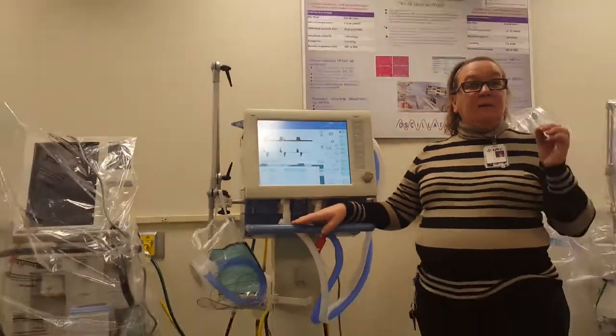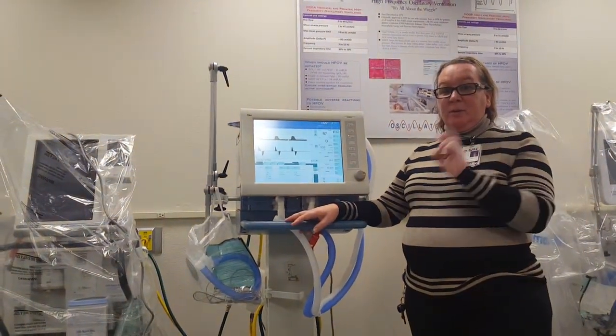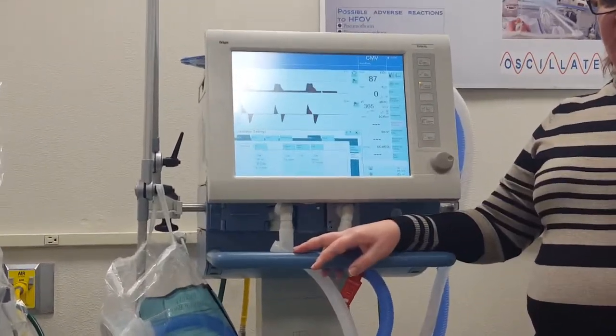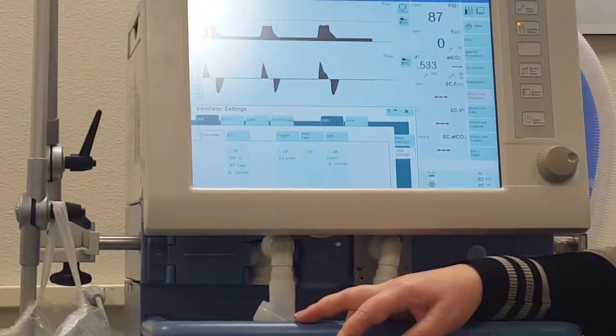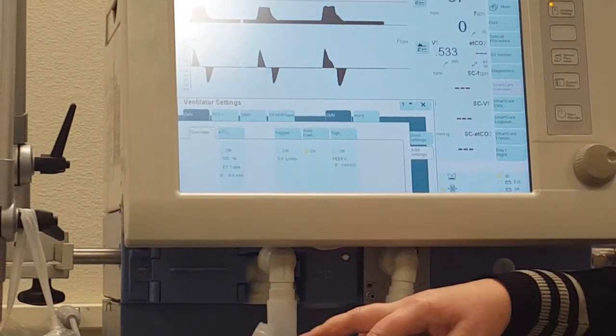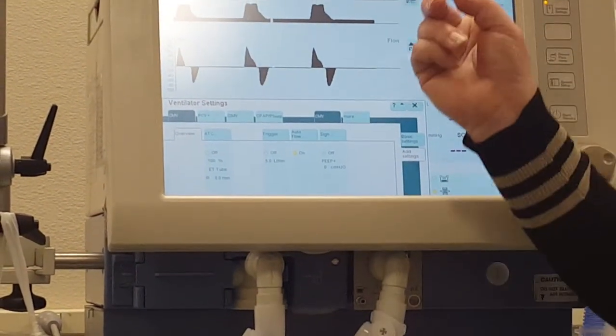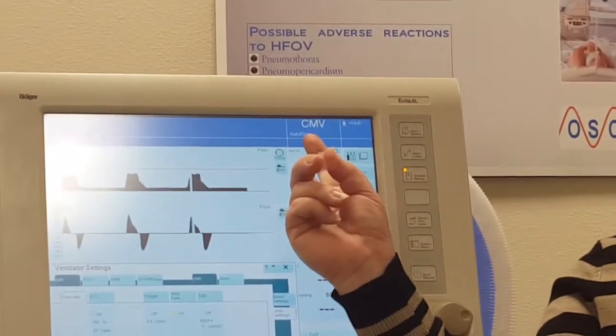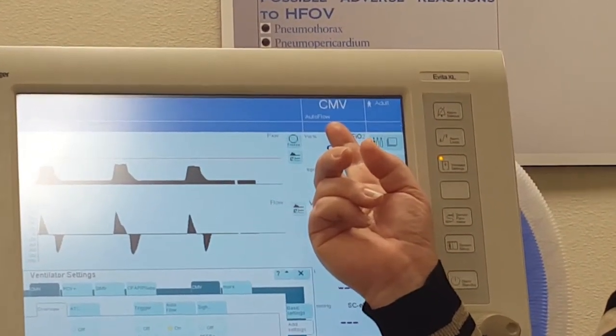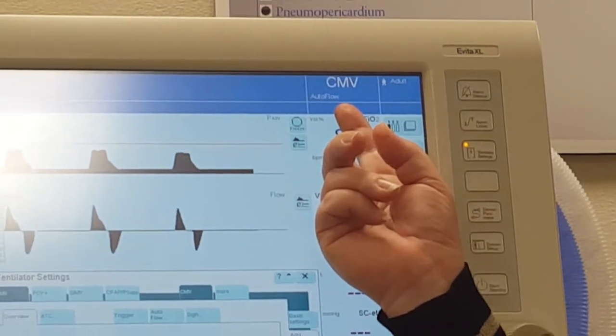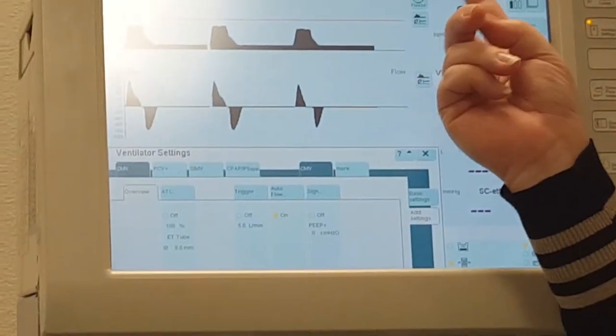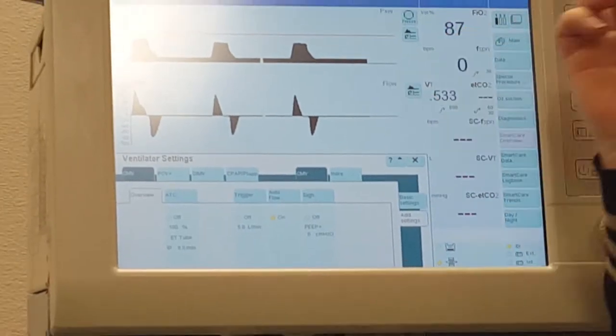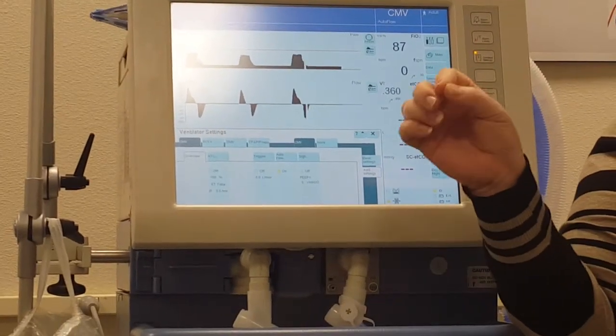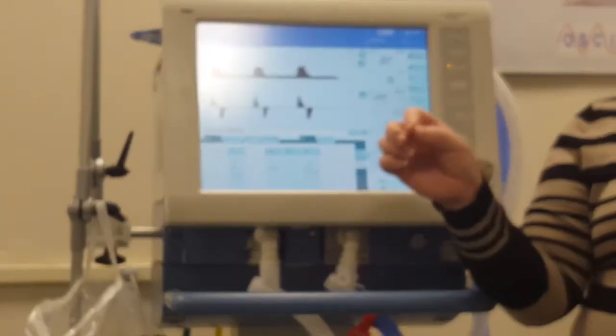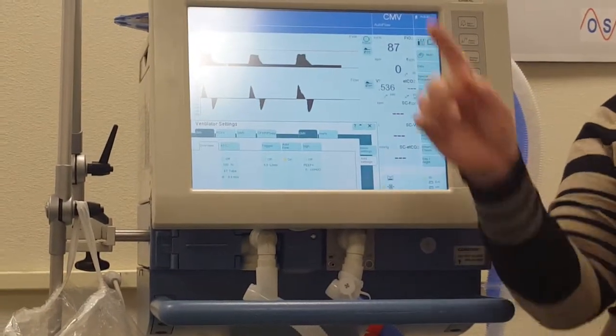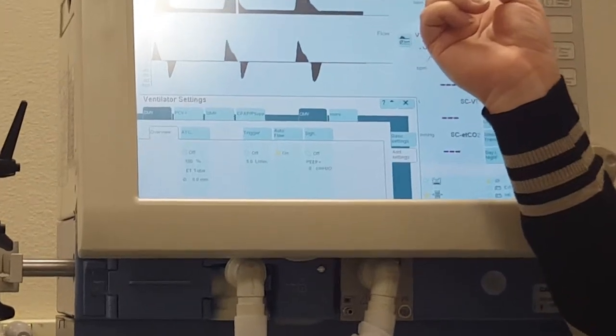So CMV without auto flow would be ACVC, the very first one I told you. If you're in CMV with auto flow, it's ACPRVC. And you'll see the word auto flow right up here underneath the word CMV. So when I come over to your vent and I tell you you're not in ACVC, even though you think you are, it's because you didn't turn the auto flow off. The reason I tell you that is because it defaults to being on a lot. So pay attention to your settings. If you want to be in ACVC, you actually have to go turn auto flow off if it's on.